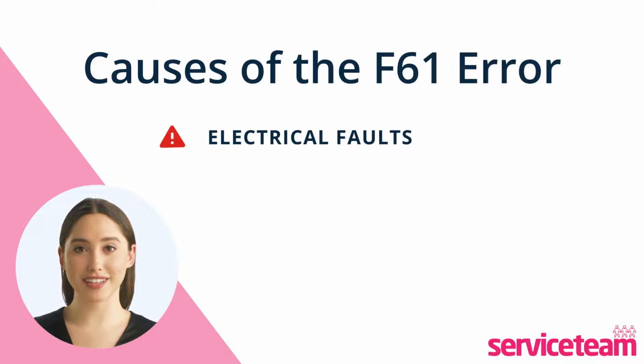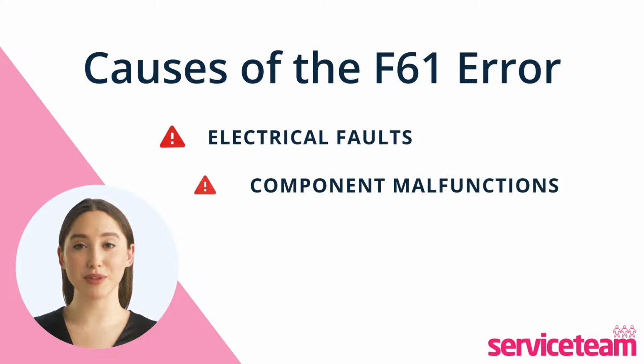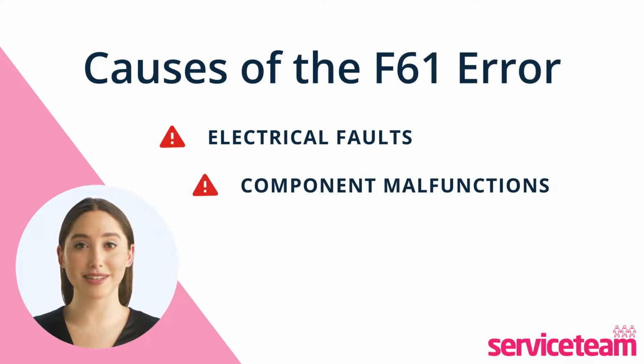Another cause of the F61 fault code is the malfunction of boiler components. These include the gas valve, ignition lead, electrode, sensors, pressure, temperature, fan, pump, combustion chamber, and burner. These issues can interrupt the boiler's operation and lead to the error code.